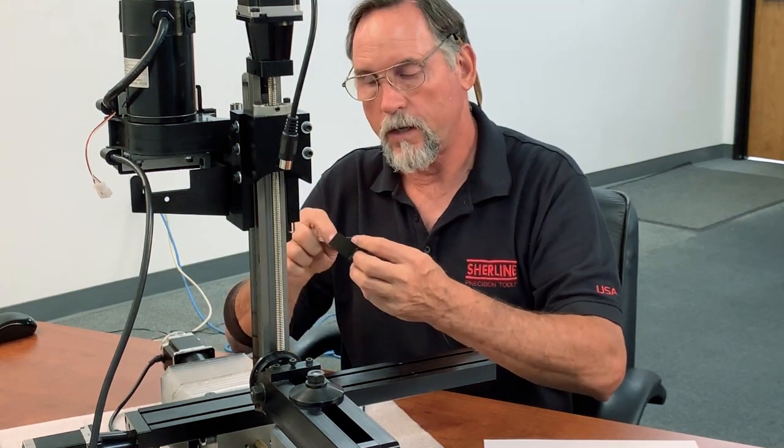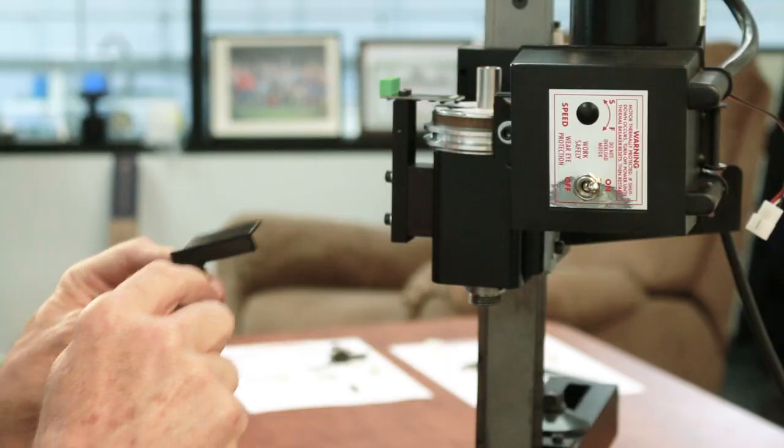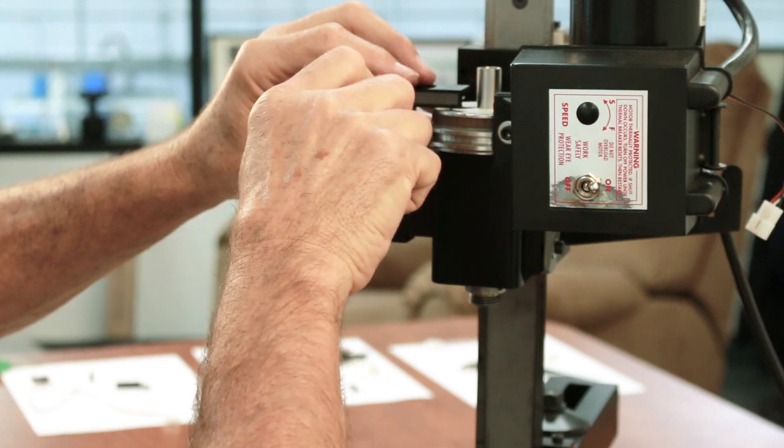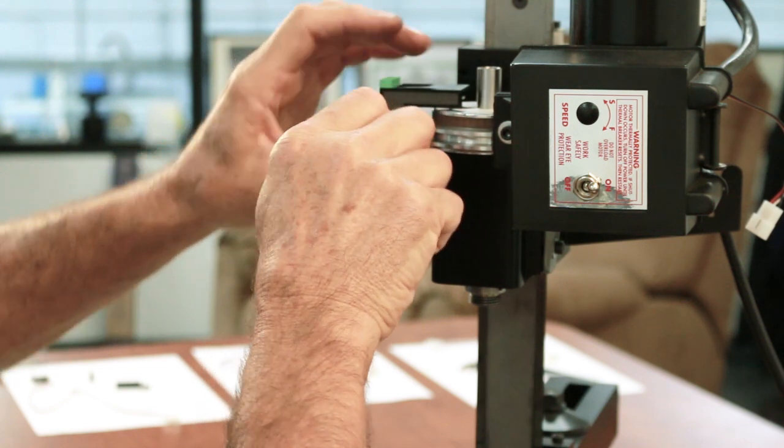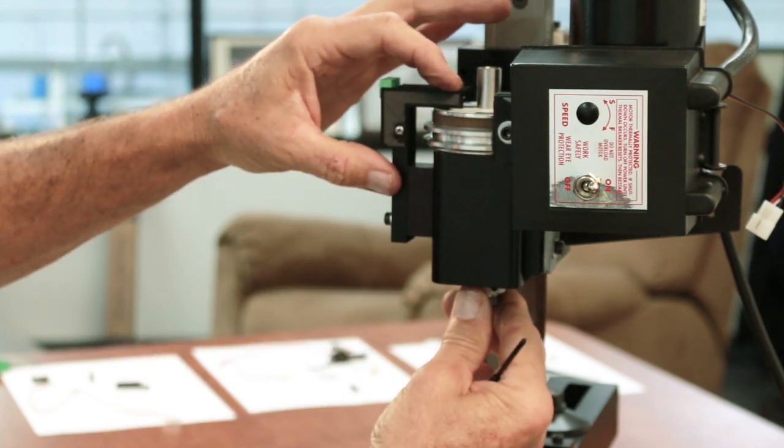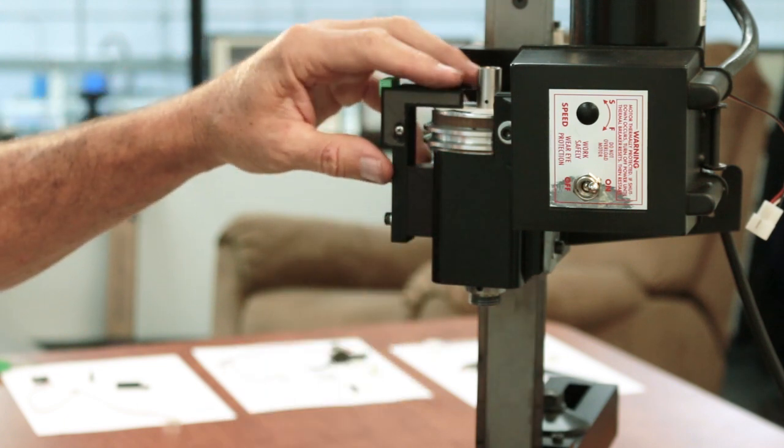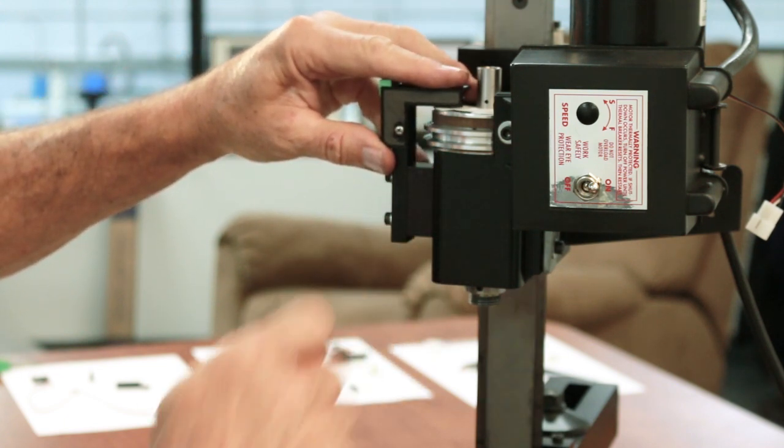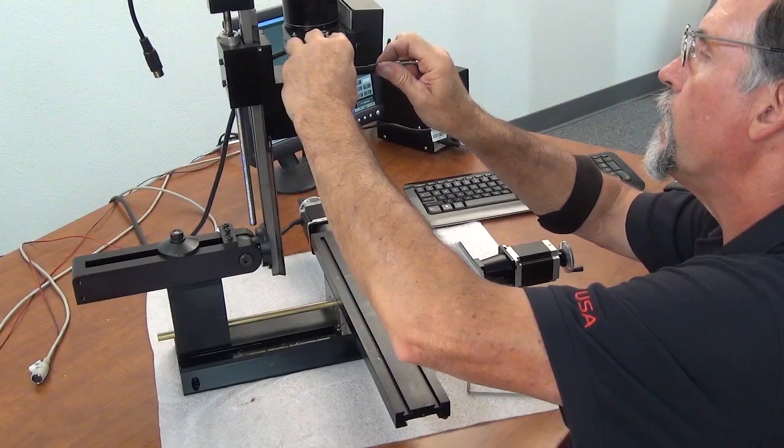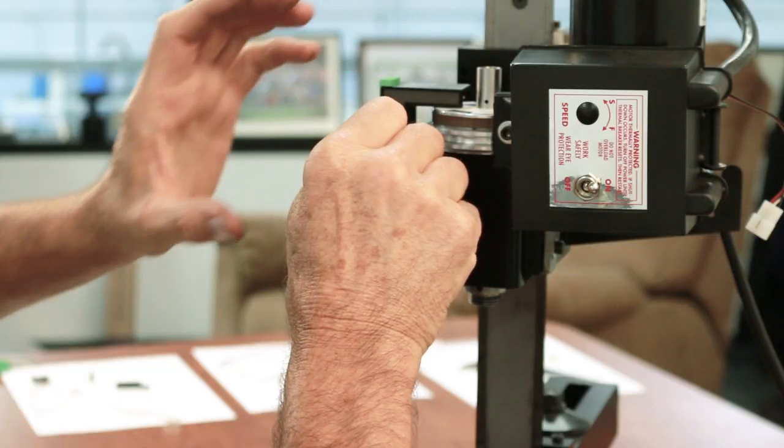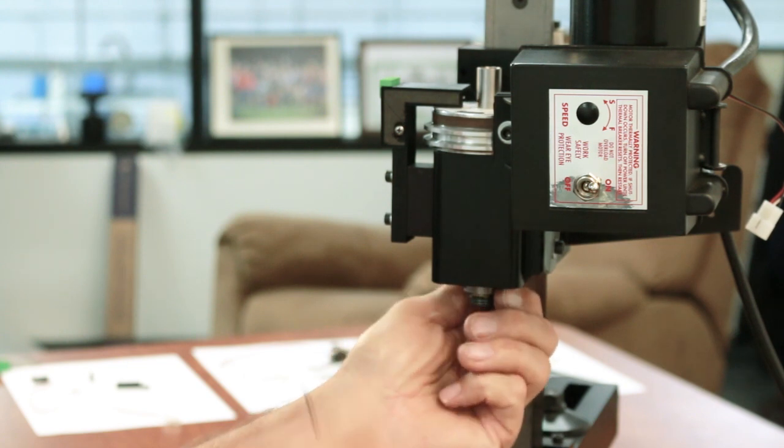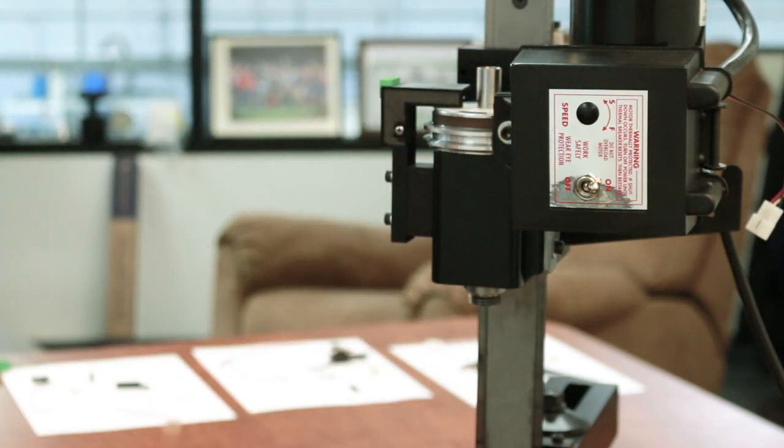We've got one screw, and it's just a little Phillips head button screw that goes through and holds the encoder cover in place. You can put it on there. Now, if you look straight in here, right now it's touching the actual label. You don't want it to touch the label. What you want to do is pull it up just a little bit. Get it nice and square, pull it up a hair, and snug this down. If you're off a little bit out of square, just loosen it up a little bit, and you don't want it to rub on your label at all. So right there is just enough clearance on the label, and it's still shielding from exterior light on the LED.